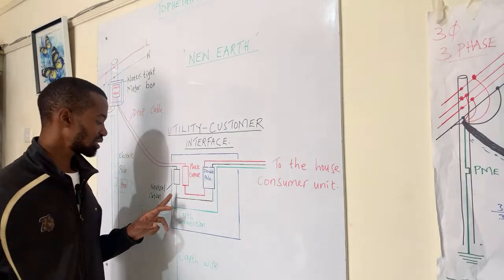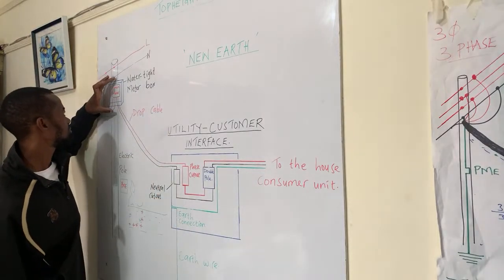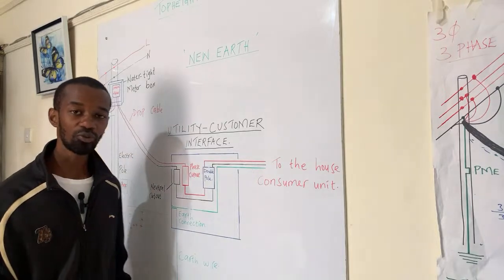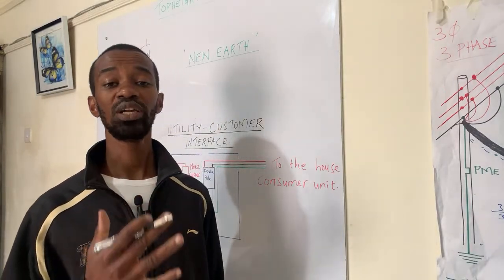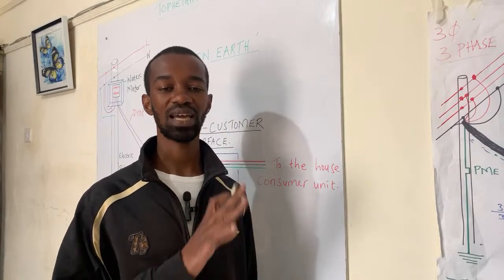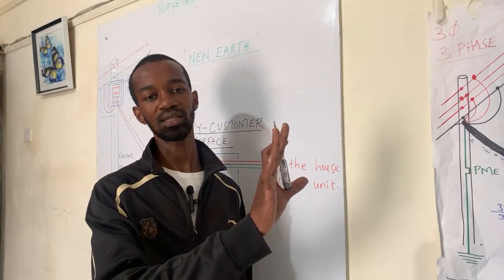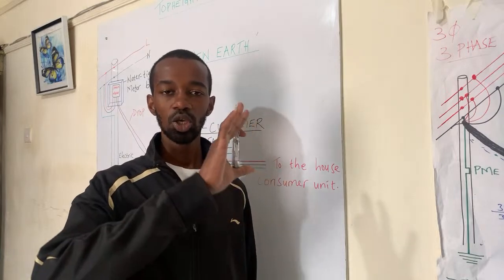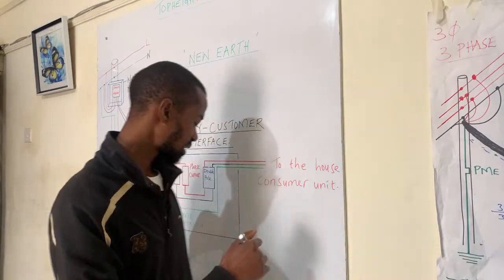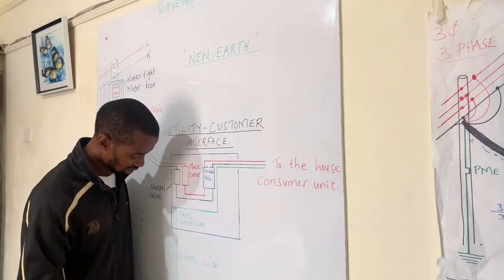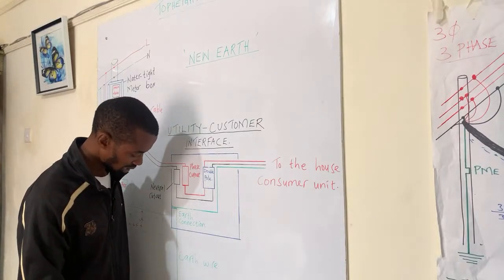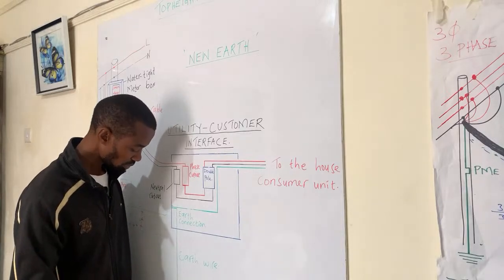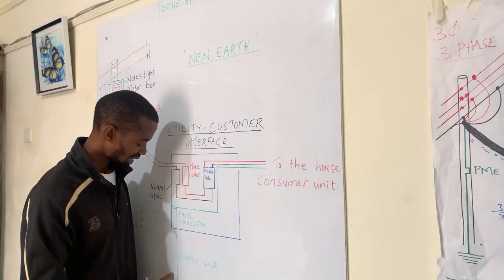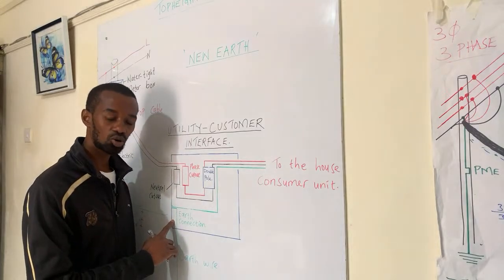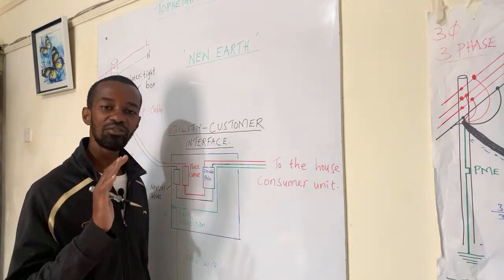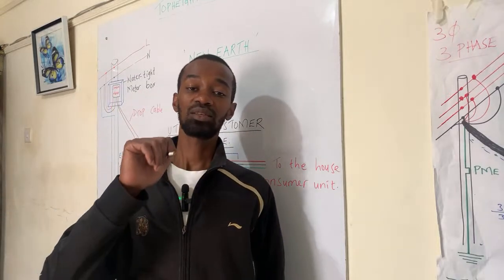When it comes to this setup whereby you have an energy meter at the pole, it is important for you to ensure that the earth connection is kind of independent at the domestic setup or at the industrial setup, whereby you come up with the earth rod or the earth pit. You know, when you are setting up the earth rod, you have an earth pit where the earth rod will be immersed.